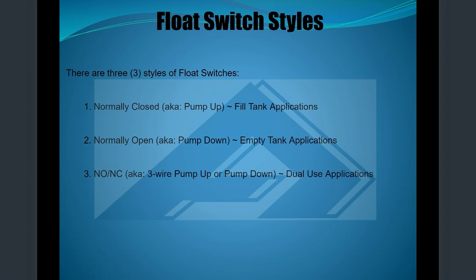When you have normally open float switches, as it's hanging down, the circuit's open. So then when it rises up, it closes, then activating a high-level alarm. Or like on a well system, that would be your high-level alarm. Your tank is full, shut off my pump, things like that. And in a sewage application with the pump switch, right now it's open, but as your sewage container is filling up, now it closes, and then it turns your pump on to pump that liquid level down, and then it'll reopen, turns the pump off, opens the circuit.